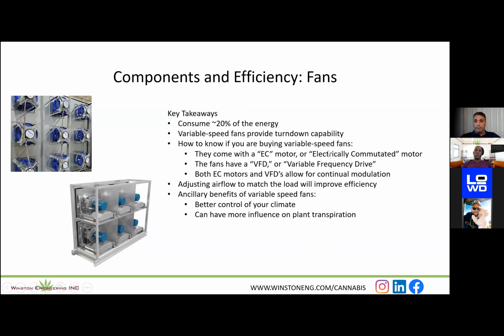So what do we look for when we're looking for these types of fans? There's really two things you're looking for. There's what's called an EC motor or an EC driven fan. EC stands for electrically commutated motor. What you're looking at over here is an EC fan. The big difference you're going to see between this fan and what you would probably call a normal fan or an AC fan is the drive. It's going to be this motor right here. You'll notice you don't see that motor over here. You see a bunch of cables coming out of there. Those cables are essentially programming that fan to maintain a certain static pressure or a certain airflow, and it's going to ramp up and down as the conditions change in the space to match what you programmed it for.